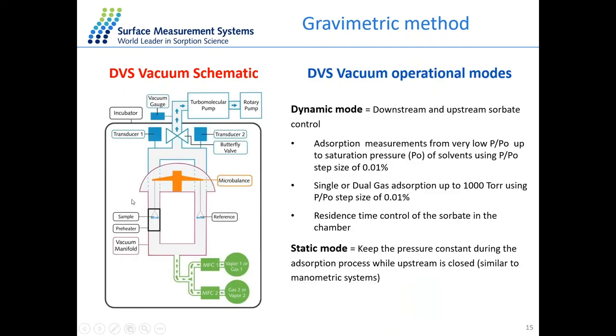The system consists of a vacuum chamber with a balance. From the balance, two hang-down wires are suspended: on the left-hand side is the sample, and on the right-hand side is the reference. Around the sample side, there is a high-temperature preheater to outgas samples in situ. The system also has two baratrons to measure absolute pressure, two MFCs for upstream control, and a butterfly valve for downstream control. Outside, there is a vacuum gauge for in-situ monitoring of outgassing.